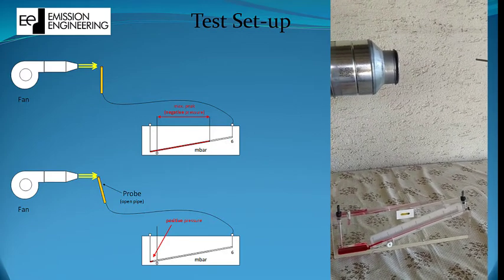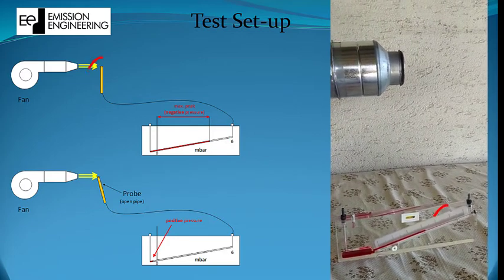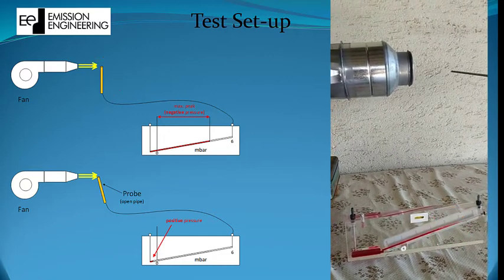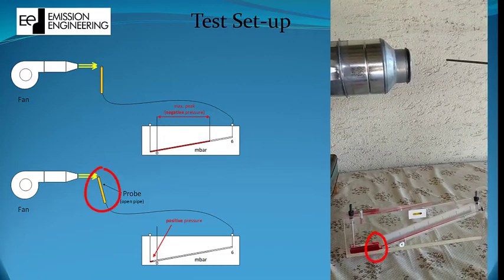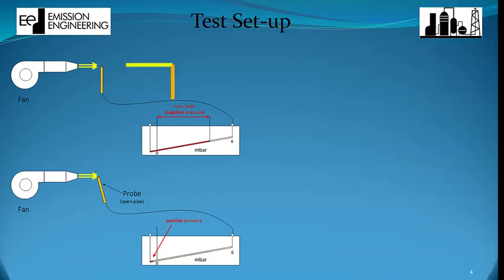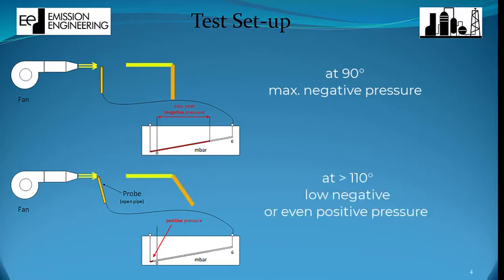If air passes the tube on a 90 degrees angle, there is a suction or negative pressure created up to approximately minus 5 millibar or minus 51 millimeter water column. Whereas if that angle is inclined to the air flow, it can get positive.